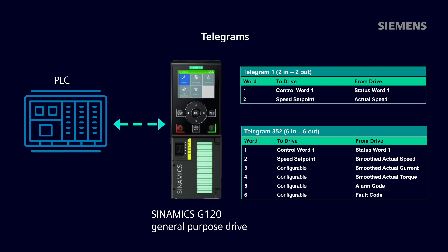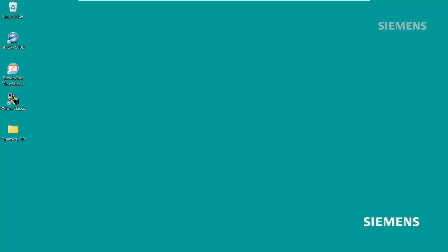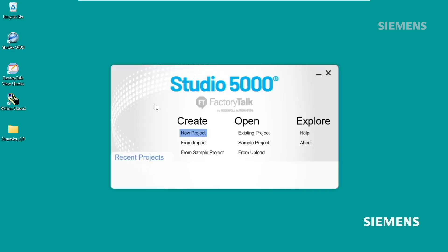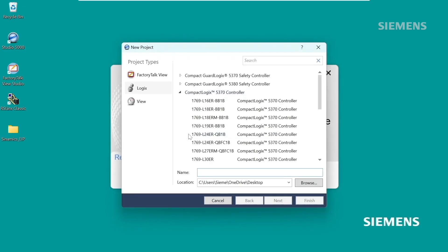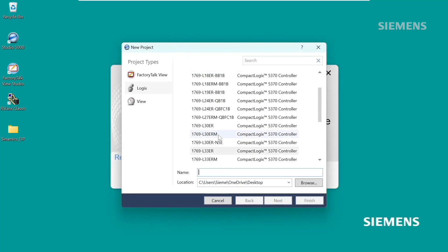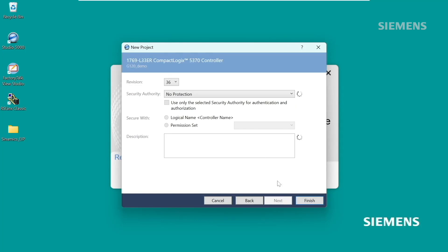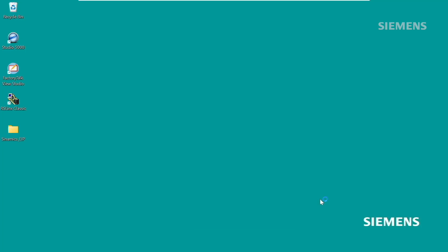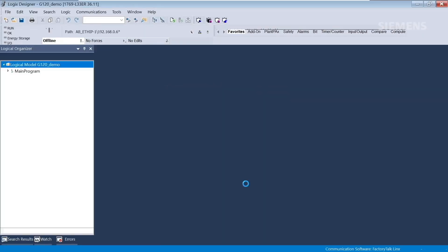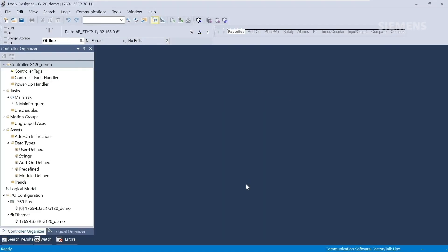Once you are finished commissioning the drive, you can add it to your Studio 5000 project. Let's open Studio 5000. We'll create a new project and select the controller that we're using, a CompactLogix, and click Finish. You can see that the CompactLogix PLC has been added to the project tree. Now we'll register the Sinamics Electronic Data Sheet. The Sinamics EDS file is not firmware dependent, meaning you do not need to manage firmware revisions when adding or replacing a drive. There is one EDS file that can be used for any Sinamics drive.